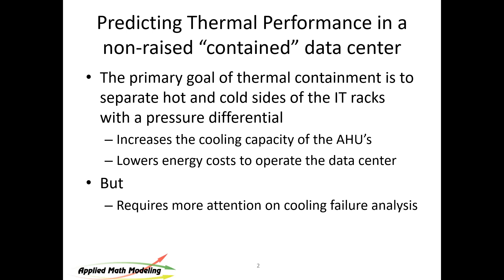Containment also requires attention to cooling failure analysis. One downside is that if you have a cooling unit failure, your data center is at more risk than if you did not have containment — simply because you've compartmentalized the hot or cold and don't have the overall room volume as a buffer. We refer to these as transient studies, which I'll cover in the next webinar. Today's session will be steady state, focused on containment of the hot aisle.